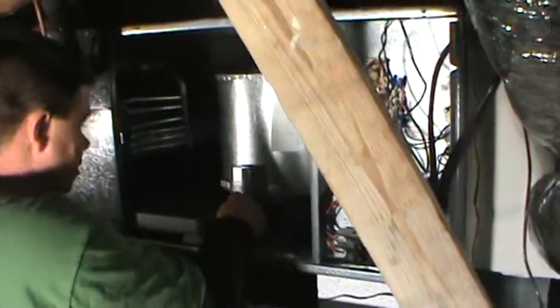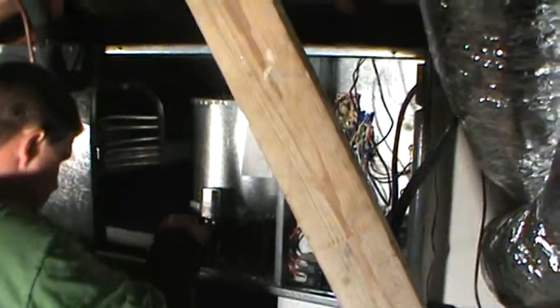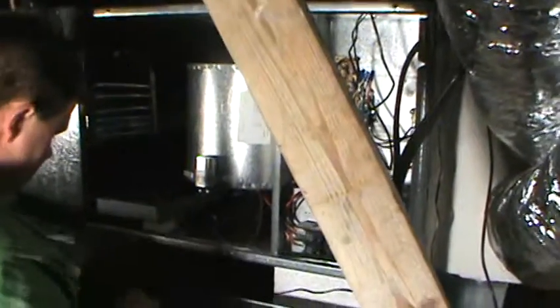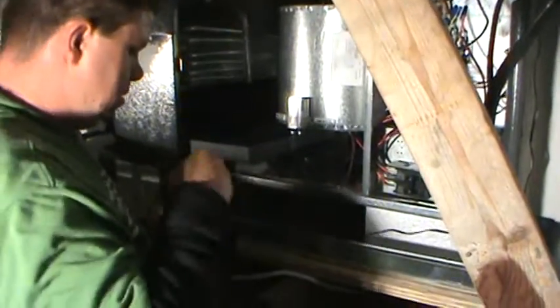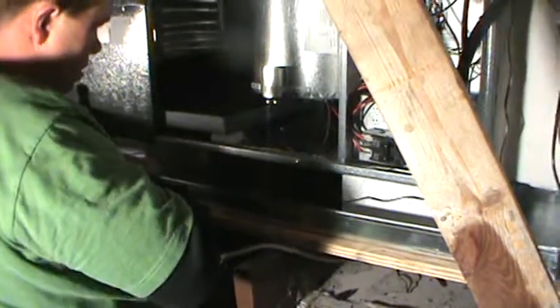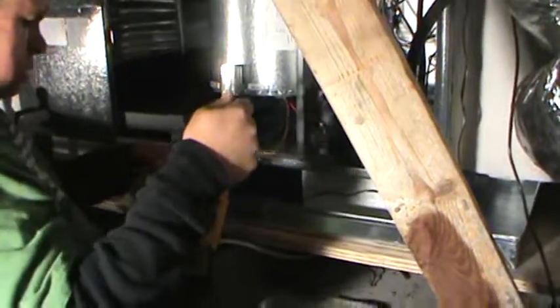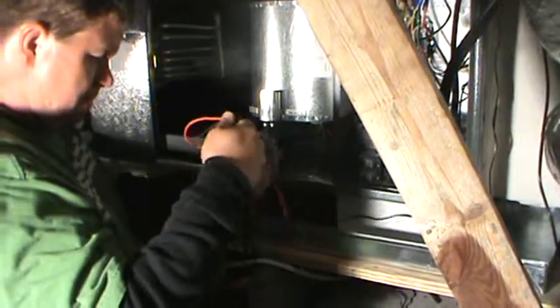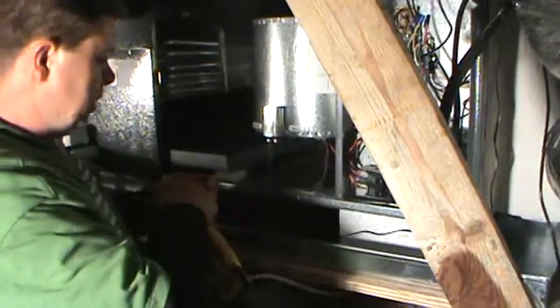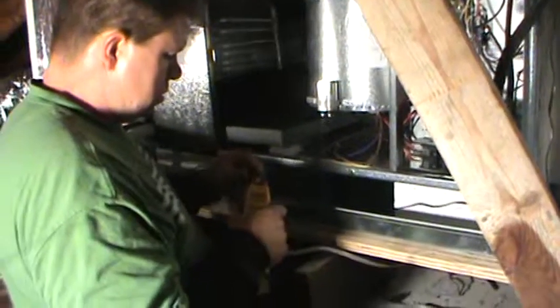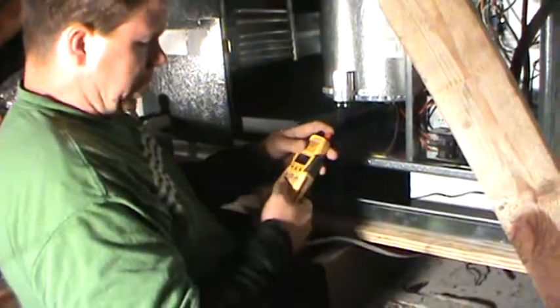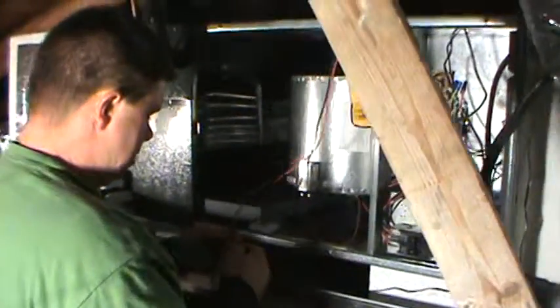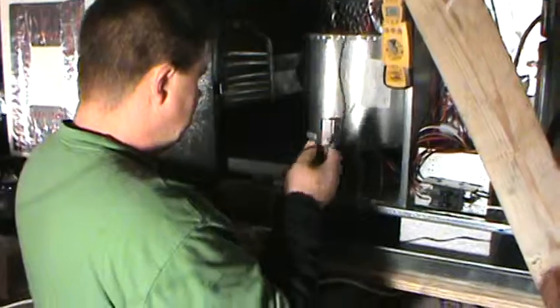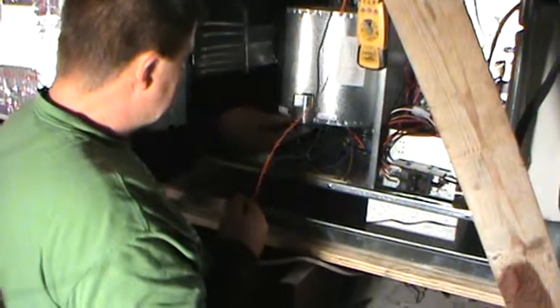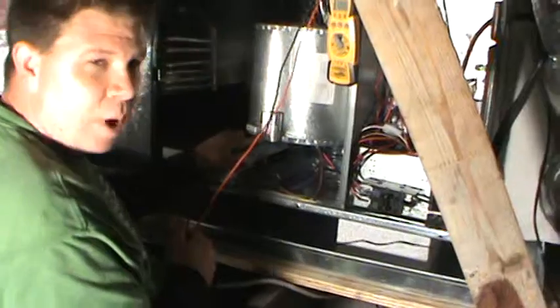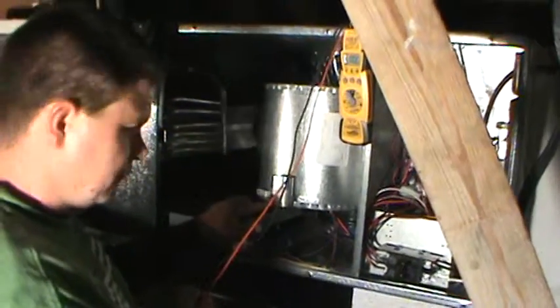Remove your wires from the capacitor. Okay. That's where the multimeter is going to come in. Get your leads put on. And you're going to want to set your meter to microfarads. Now you're going to need to, of course, check the capacitor, see what size it is. It'll be listed in UF or in MFD. A lot of times you'll see the UF though.